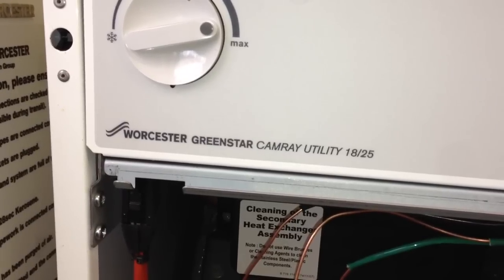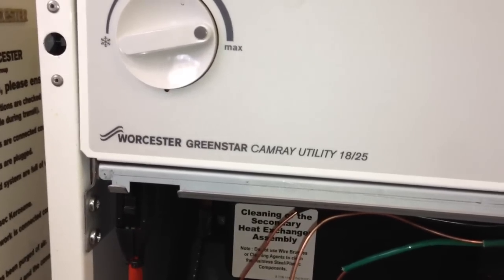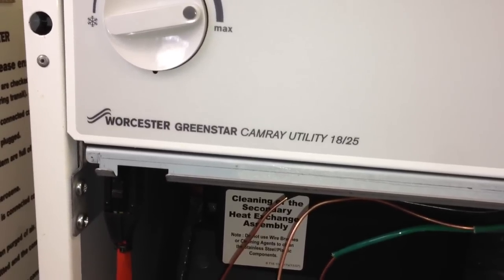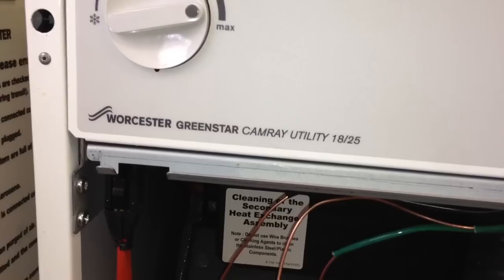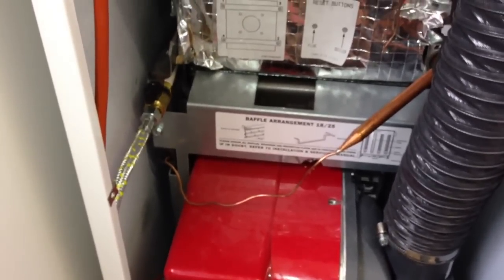This is looking at a Worcester Greenstar Camray Utility 18/25, which is an oil fire boiler. The situation is as such: the oil has run out and the boiler has gone into lockout. The lockout light is just down here, and you can see it is lighting up every time the boiler tries to fire.